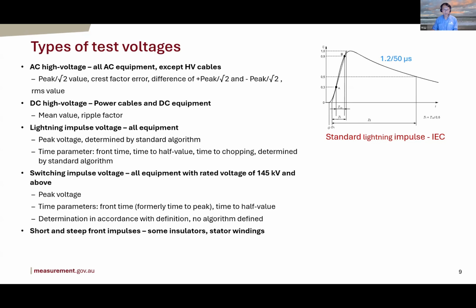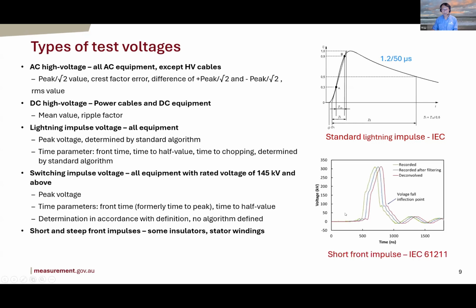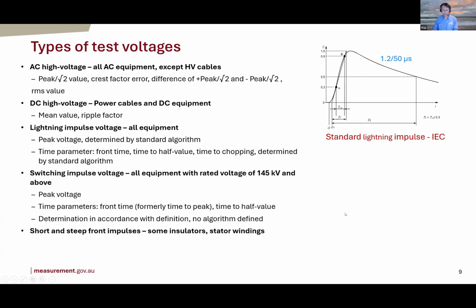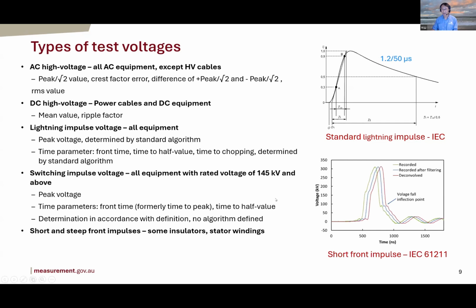And you also have the short and steep front, which is a new type of, well, it's not really new, but it's another type of pulse, much faster than the lightning impulse, which has a typical rise time of a few hundred, about 200 nanoseconds instead of 1,200 nanoseconds. So again, peak voltage and rise time, and the standardization in this area needs to be further developed.